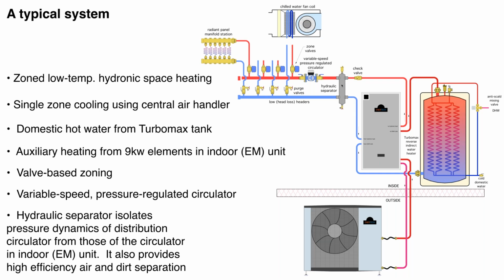And in addition to keeping the peace between these 2 circulators, this is also providing your high efficiency air separation in the system. So we get the micro bubbles out of that fluid. And in the bottom here, in a lower portion, it's also acting as a dirt separator. So it's really 3 functions. Many of the newer ones also have a strong magnet at the bottom. I'd recommend that anytime you're using high efficiency circulators. And the reason for that, the high efficiency circulators have very strong permanent magnets in the rotor, and you don't want any iron oxide particles flowing through the system. The circulator manufacturers certainly take steps to minimize the impact of that, but the cleaner that fluid is, the better.